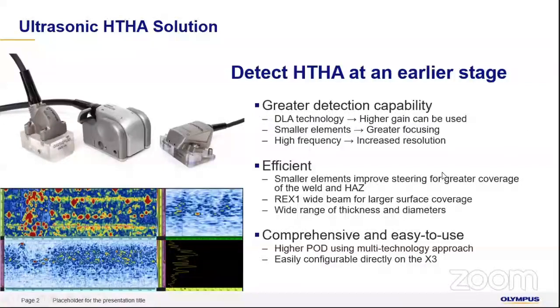With smaller elements, our physical ability to focus within the component is also increased. With higher frequency, using a higher frequency probe gives higher resolution, which improves detectability. When we combine all three of these techniques and use them for detection of HTHA, we will get much better results.